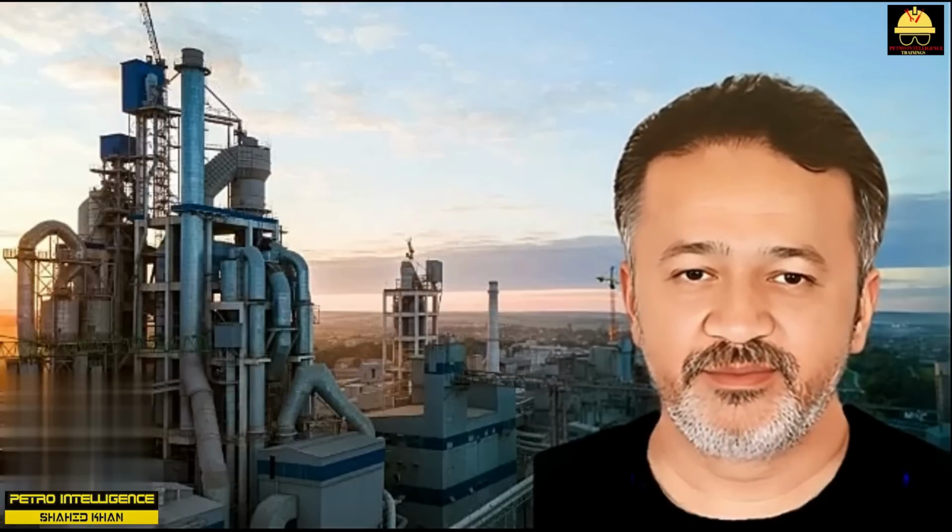Terminal tube velocity. Have you ever seen a heat exchanger tube bundle pulled? Perhaps many of the tubes were bent and twisted like partly cooked spaghetti. This distortion could not be very good for the shell side heat transfer. The cause of the bent tubes is called terminal tube velocity. Let me explain. Let's assume we have a new heat exchanger. The fluid on the tube side is crude oil.